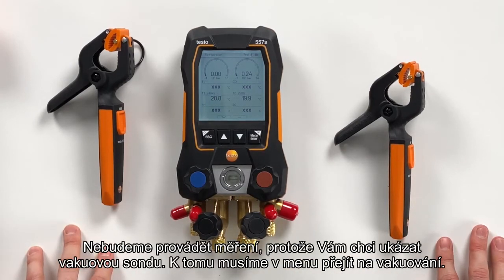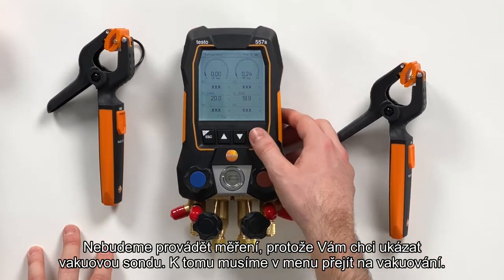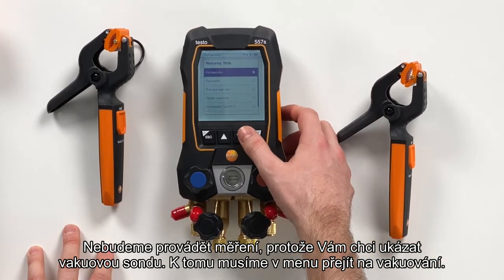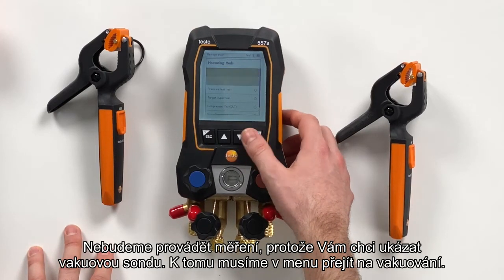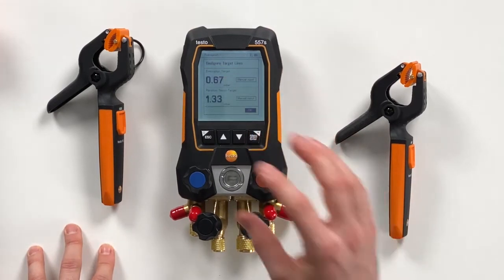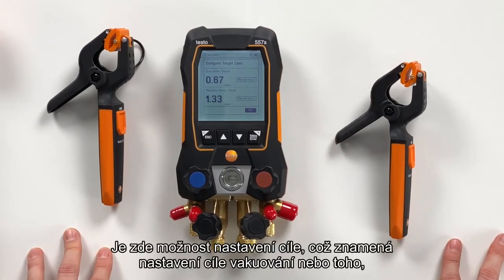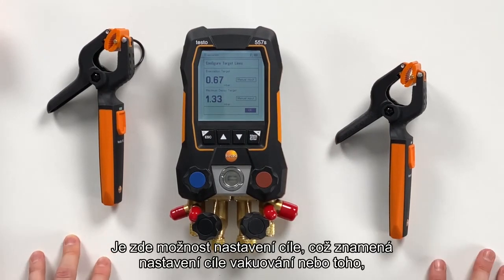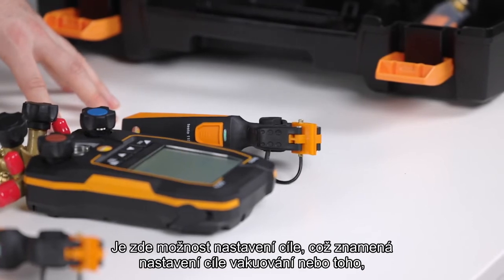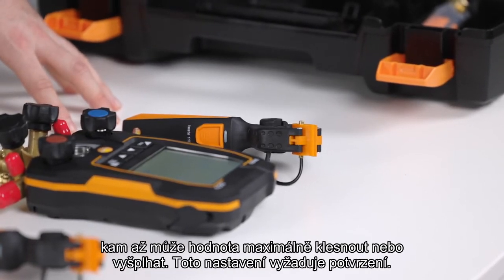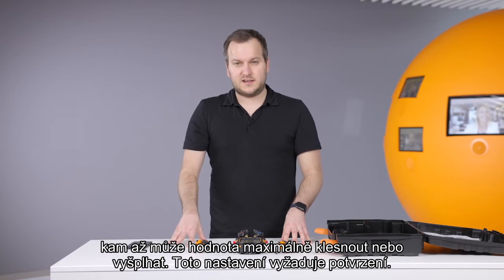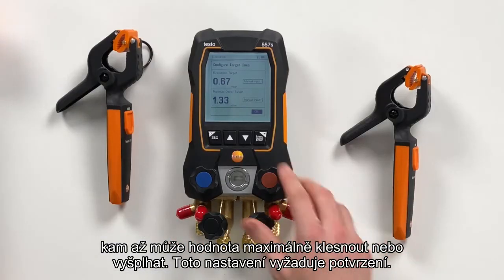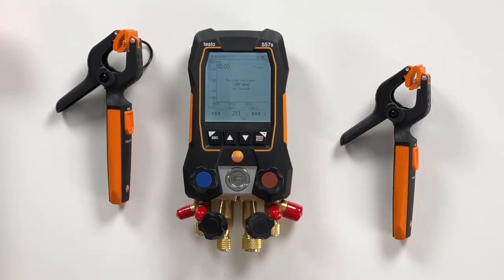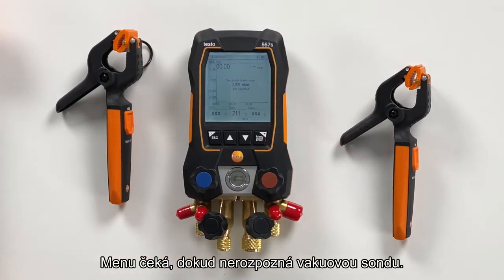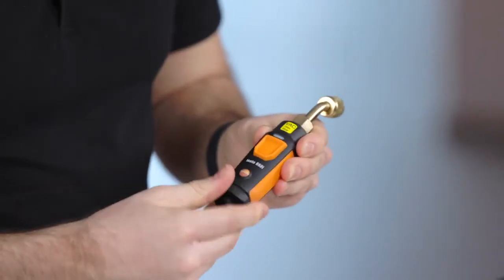This we will not do now, but we will also show the evacuation mode. Therefore, we navigate through the menu to the evacuation measurement. Here, the new thing on the user interface is that you can configure target lines. How deep do you want to pull down the vacuum, and what is the maximum decay that is allowed. We confirm this just right now, and then this menu is waiting for the vacuum probe, which we take out of the case.